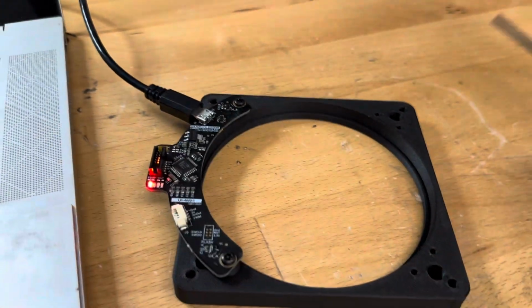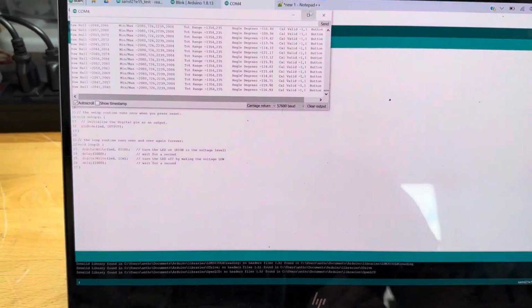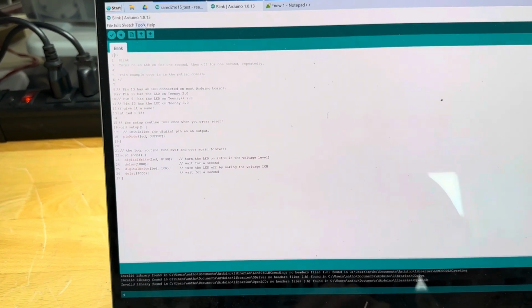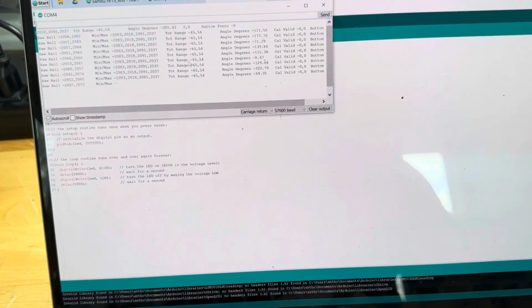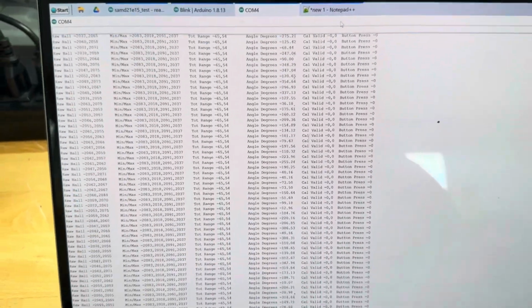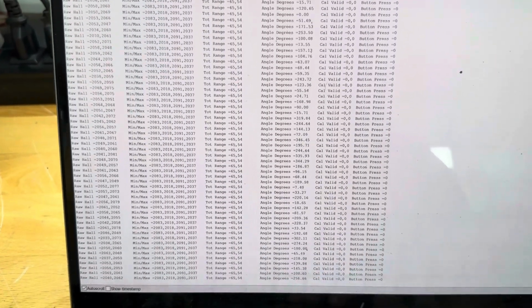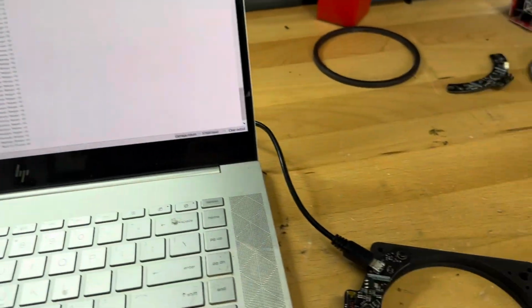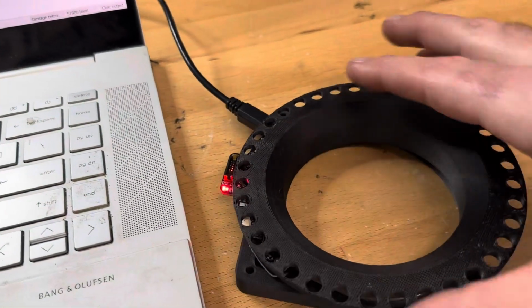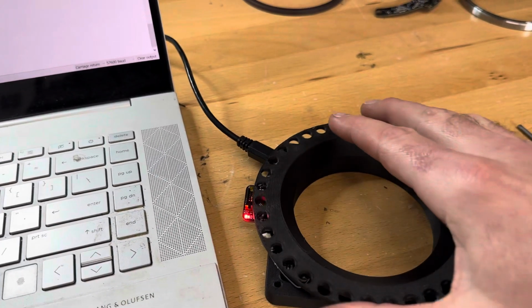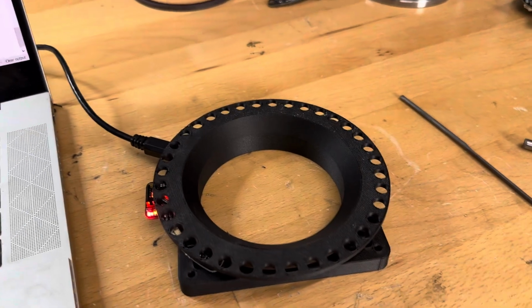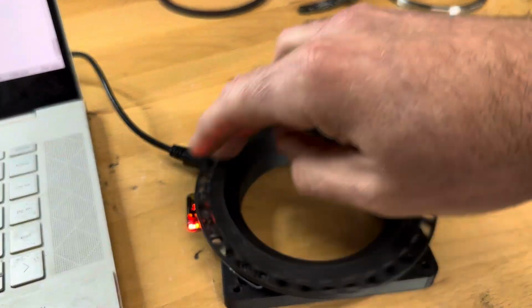Okay, now we're back to calibration. And if we open the serial port, you should be able to see that we are back to getting the calibration data from the serial port. So we are not getting degrees or anything, we're just getting that. So put the sensor back in, okay? And to start the advanced calibration, if we want to do that, we start by doing a basic calibration.